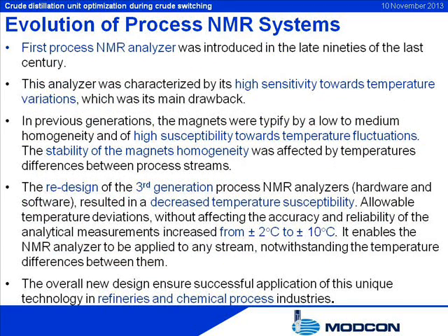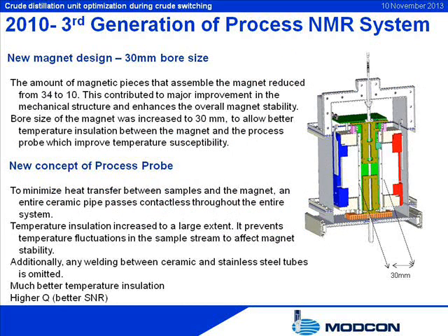The first process NMR analyzer was introduced in the late 1990s. This analyzer was characterized by high sensitivity towards temperature variations, which was its main drawback. In previous generations, the magnets were typified by low to medium homogeneity and high susceptibility towards temperature fluctuations; the stability of the magnets' homogeneity was affected by temperature differences between process streams. The redesign of the third-generation process NMR analyzers' hardware and software resulted in decreased temperature susceptibility. Allowable temperature deviations without affecting accuracy and reliability increased from ±2°C to ±10°C, enabling the NMR analyzer to be applied to any stream notwithstanding temperature differences between them.